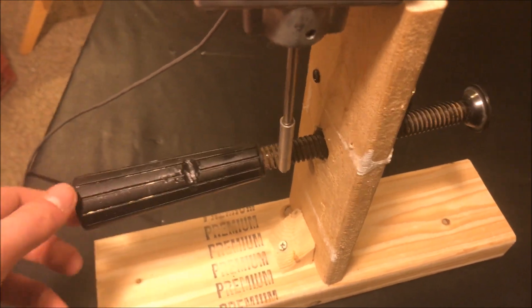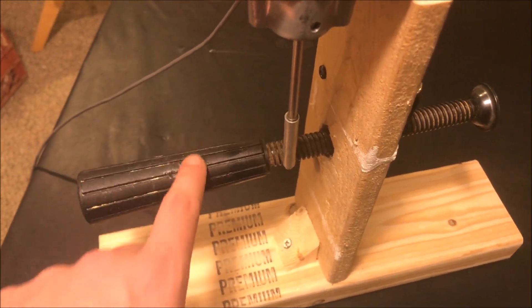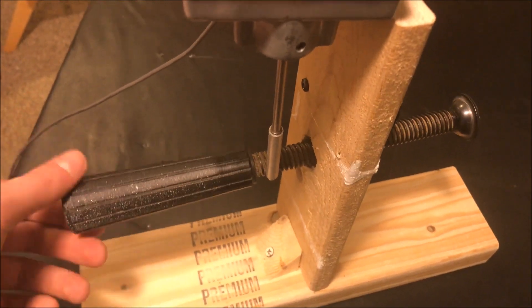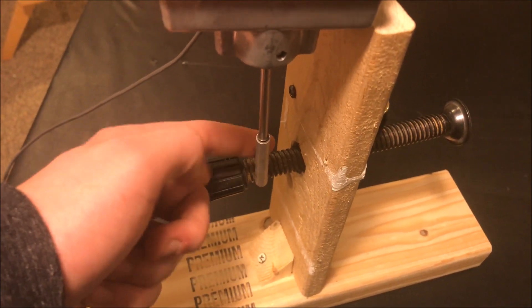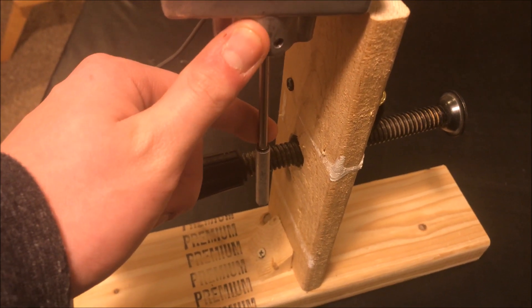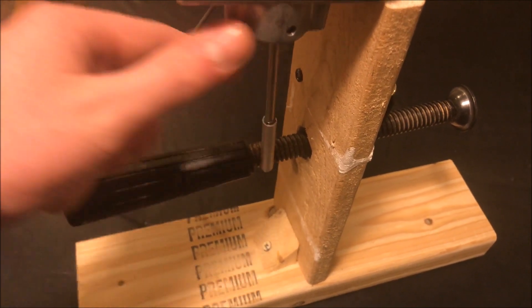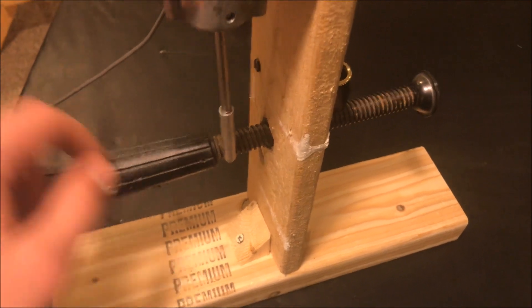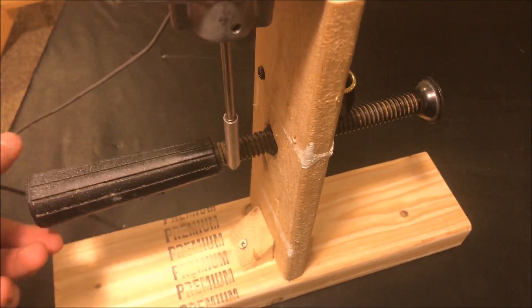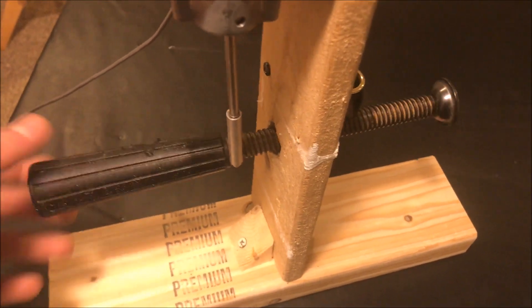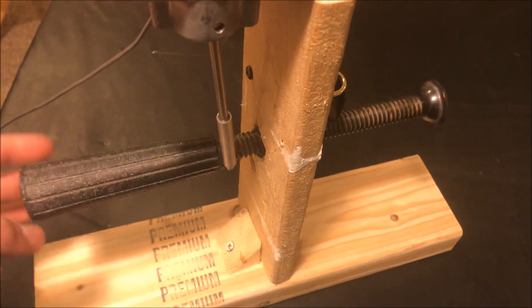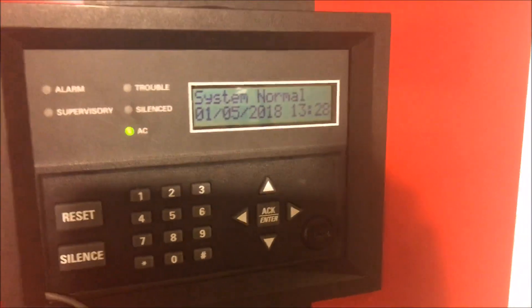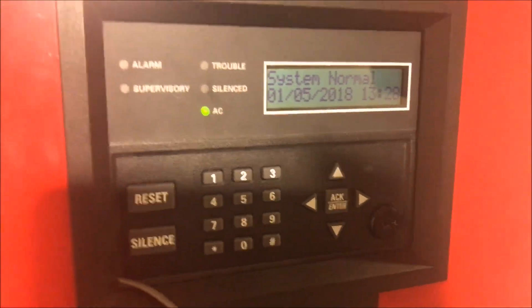And then normally there is like a groove kind of like this. I try to make a groove. There would be a groove in the stem. And that is where the stem for the supervisory switch would sit in. But right now we are just using the ridge here. So once it gets up and over that ridge, the panel will go back to system normal saying that the valve is in its normal position.